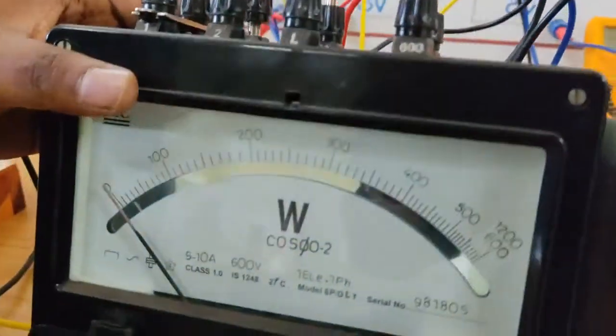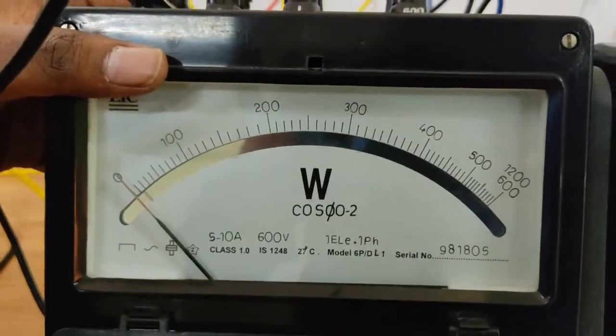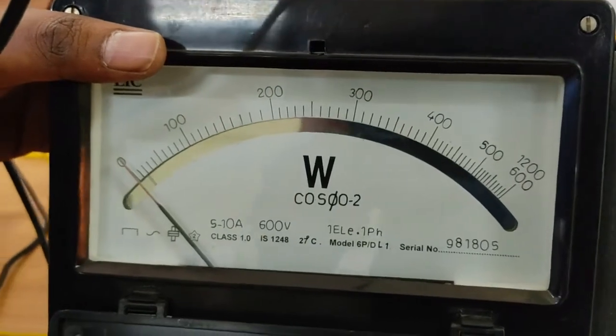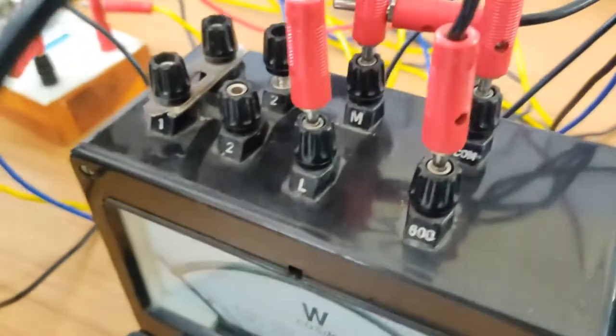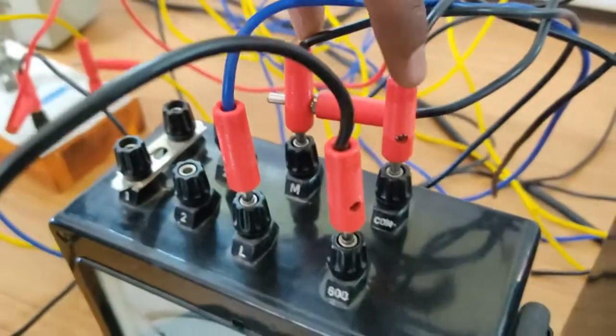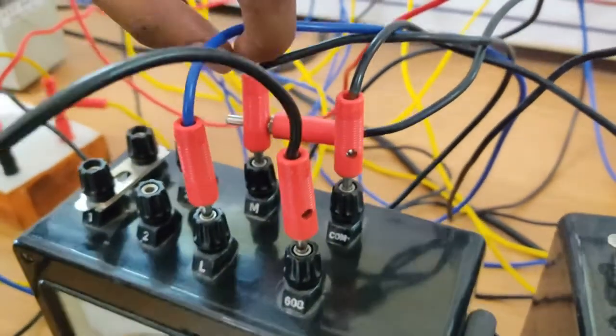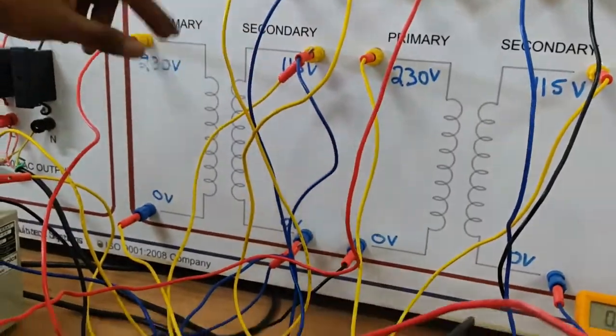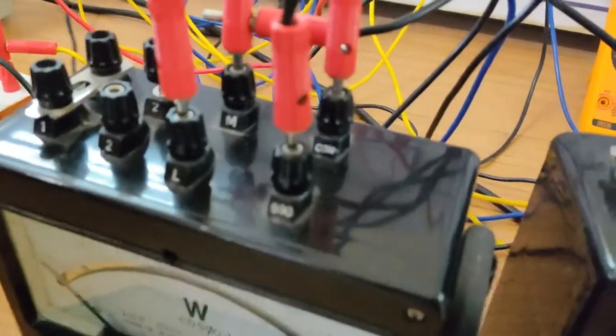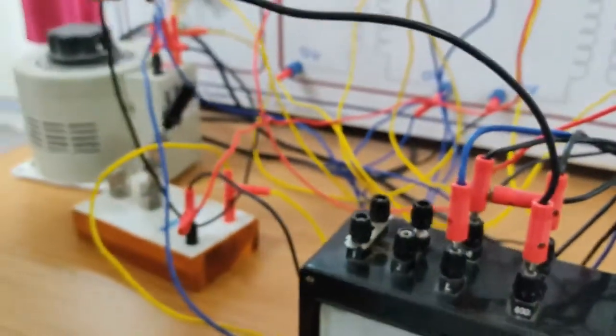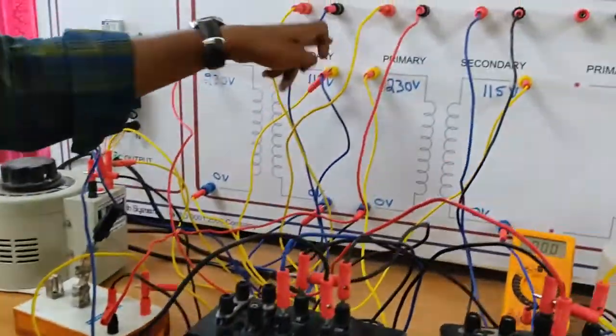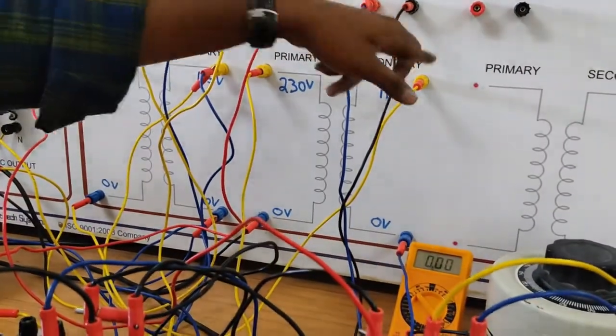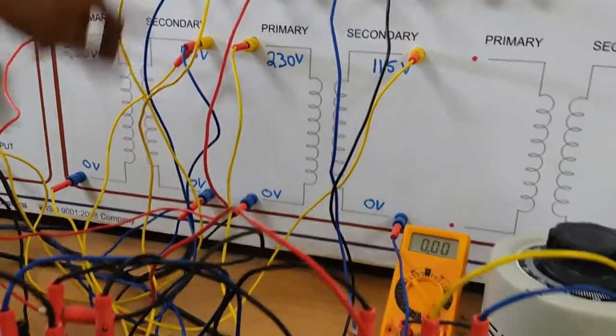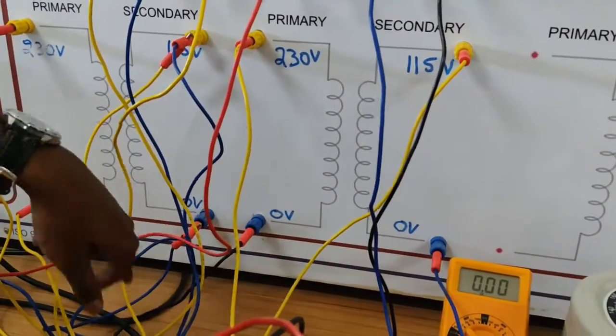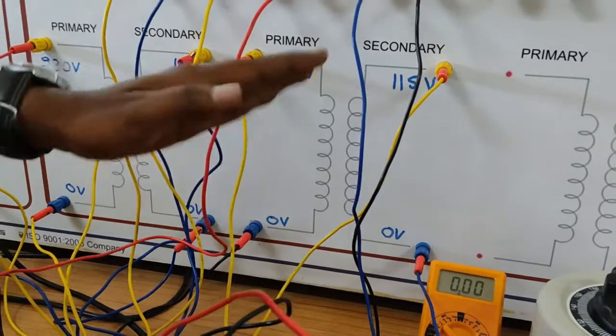This is your LPF wattmeter, which is used for inductive loads only, and low power factors. So the ammeter negative should be connected to the M terminal and MC is shorted. Next, L should be connected to the 115 volts primary of your first transformer. Next, V should be connected to your auto transformer negative supply. Clear? Next, the 115 volts terminals of both the transformers should be joined, and the corresponding winding 0 volts terminals have been shorted. This is the primary winding connection.